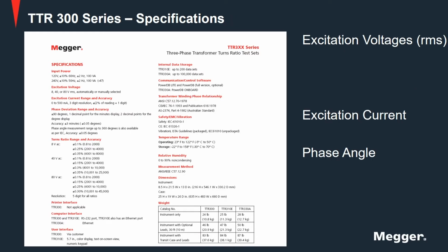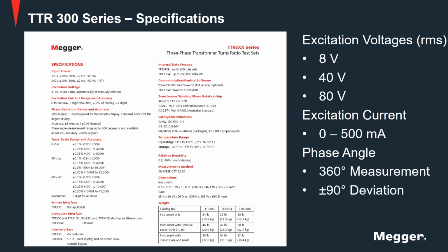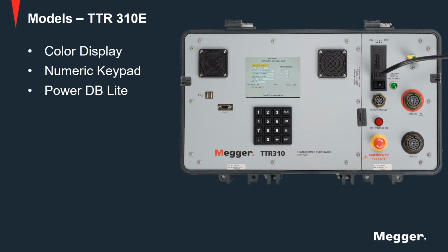Let's review specifications of the TTR300 series ratio meters. It has three excitation voltages of 8 volts, 40 volts, and 80 volts, and can supply excitation current up to 500 milliamps. It can measure phase angles up to 360 degrees and phase deviations of plus minus 90 degrees. More details can be found on the Megger website us.megger.com. There are three different models of the TTR300 series ratio meters.